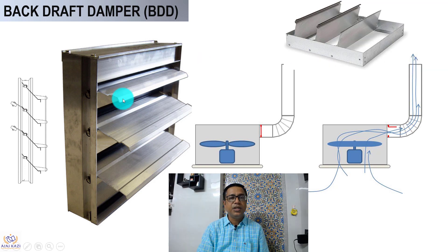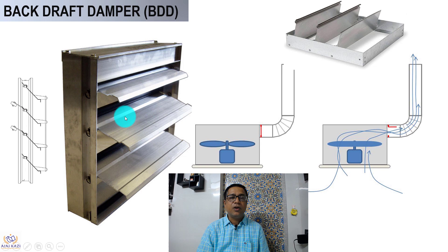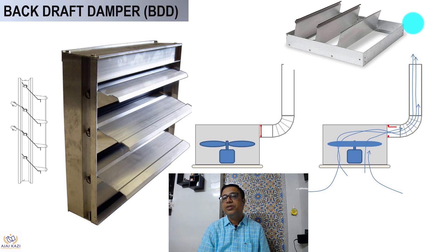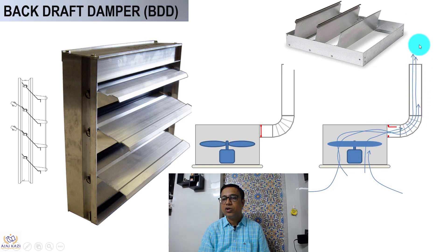Let us look further. This is a BDD — you can see it will close if the air comes from the wrong direction, and open to allow correct air flow. In this exhaust duct example: when the fan is on, the flap goes up and air flows out. When the fan is switched off, the flap closes and does not allow air to come back from outside. The air flows from inside to outside — that is the whole purpose of the BDD.